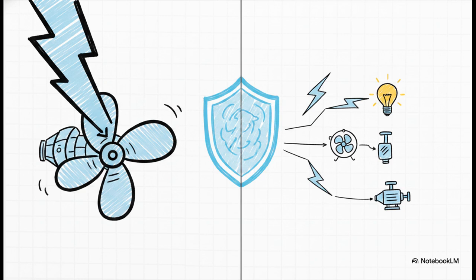Long before an emergency ever strikes, the vessel is generating its main power at a staggering 11,000 volts. That 11 kV is absolutely essential for running those massive 33 megawatt thrusters. But for almost everything else on board, the pumps, the fans, the lighting, that level of voltage is totally unusable. In fact, it's instantly lethal to standard equipment. It has to be tamed.